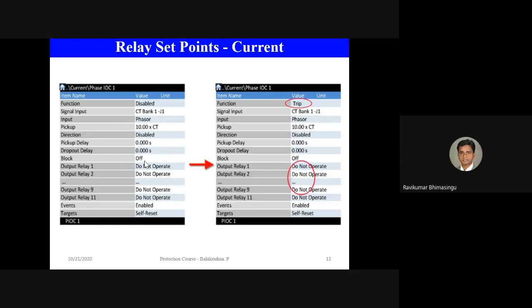Yes. So typical value of this dropout delay will be more than the pickup delay, or it will be like only for a few milliseconds? Your question is, what is the time delay that is given here, right? Yes. So for example, if pickup delay is set as, let's say, 100 milliseconds. Usually, the signal can drop at any point of time. It can drop at 20 milliseconds or it can drop at 90 milliseconds.